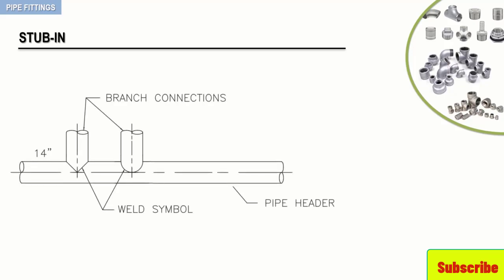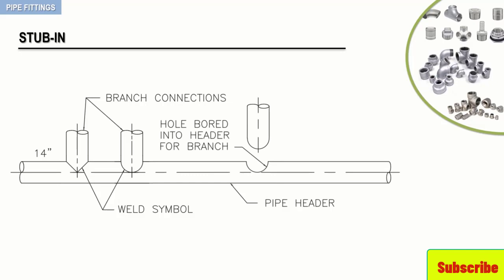The following figure depicts the attachment of a stub-in. A hole either the size of the outside diameter or the inside diameter of the desired branch is bored into the header pipe and the branch is then stabbed onto it. To make a better fit, the connecting end of the branch pipe is cut or coped in such a way as to fit around the hole that has been bored into the header pipe. The two pipes are fitted together and then welded.